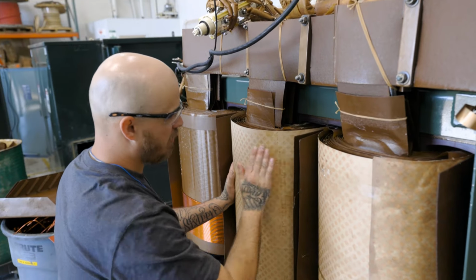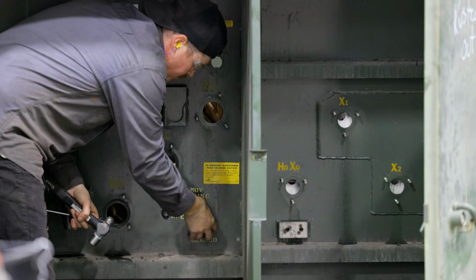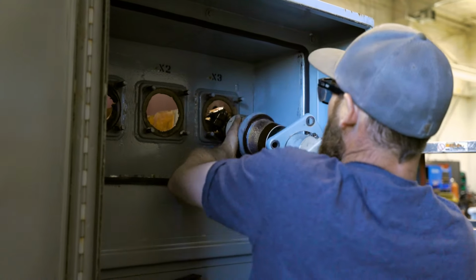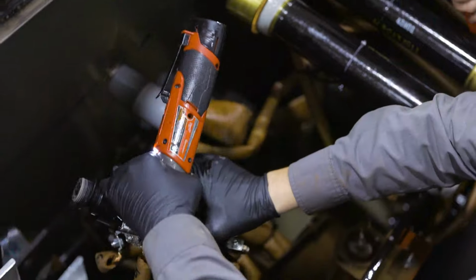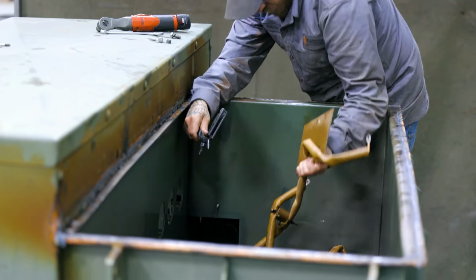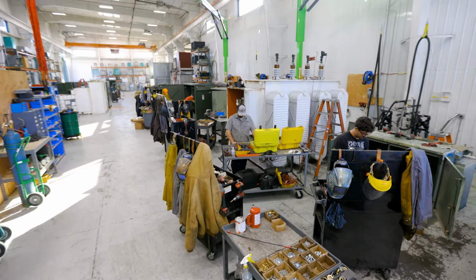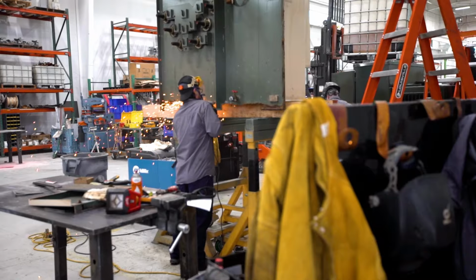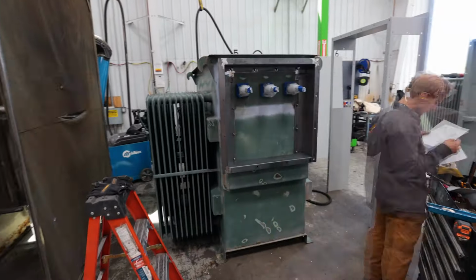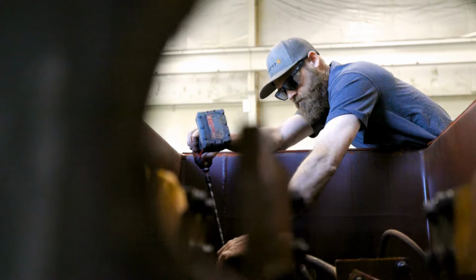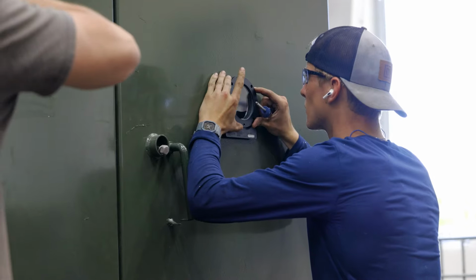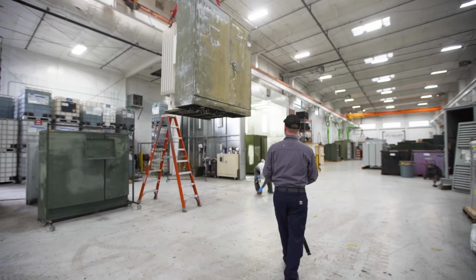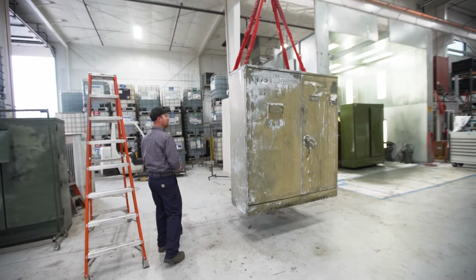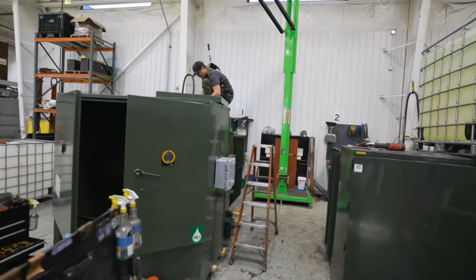If the coils are totally shot, we'll rewind some new coils for it. Otherwise, the core and coil assembly will be set aside for reassembly later. Next, our technicians remove all the bushings, gauges, and other components. At this point, we have our transformer totally taken apart. Now we can perform any tank modifications that are needed. It could be replacing radiators or the cabinet, adding custom transition sections, cutting holes for new bushing layouts, basically any fabrication needed to make the transformer meet the customer's needs. And if the old tank is just too old and worn out, we'll replace it with an entirely new tank.